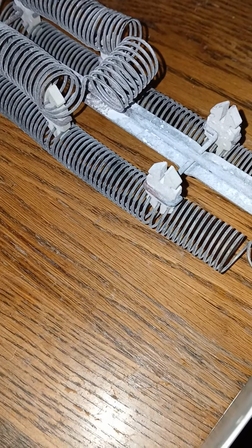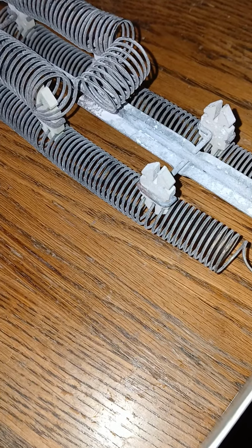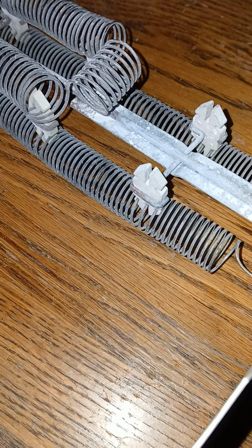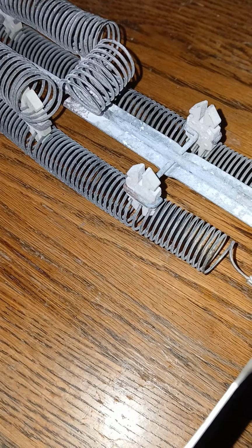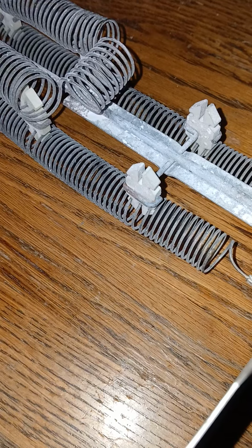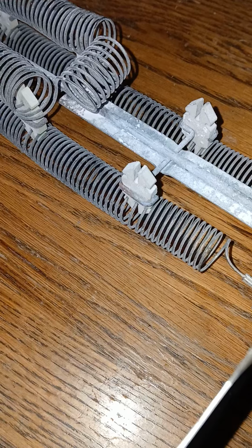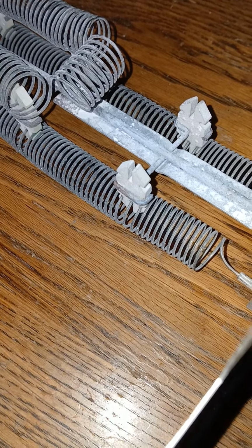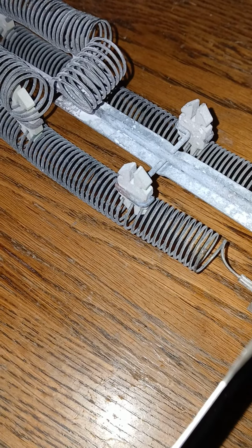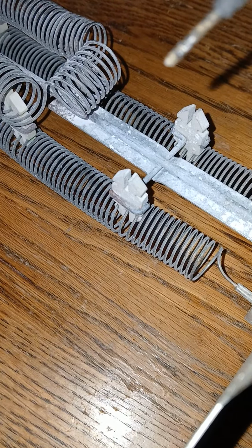This comes on perhaps in auxiliary mode, or emergency mode via the thermostat. Aux I'm assuming is the truncated version of auxiliary. The word auxiliary means helping, like an auxiliary verb means a helping verb. So it would help when it goes into defrost mode. If one throws this onto emergency heat, then at that point the outside condenser may be locked out, and this is your sole heating source.